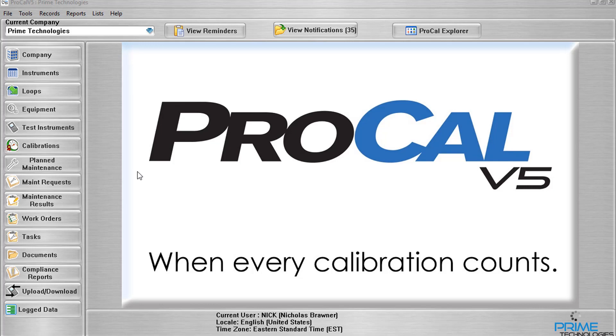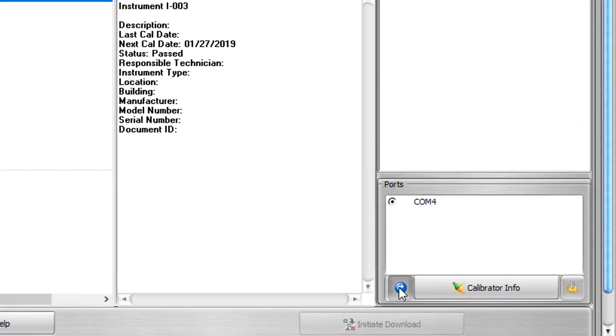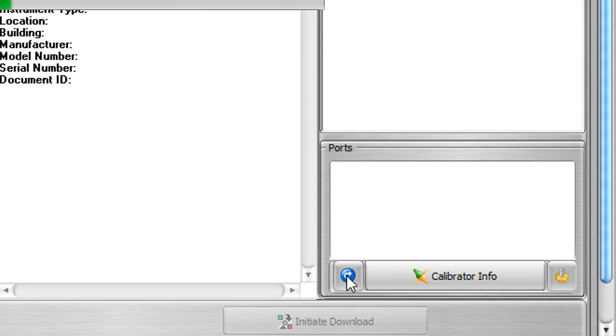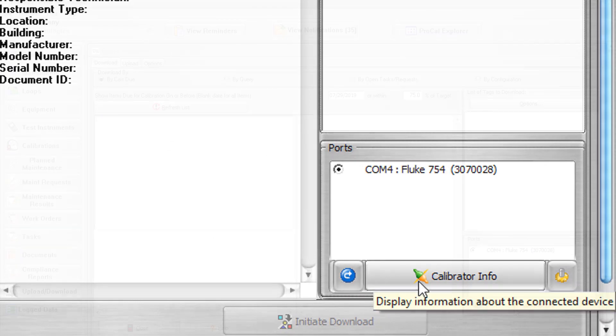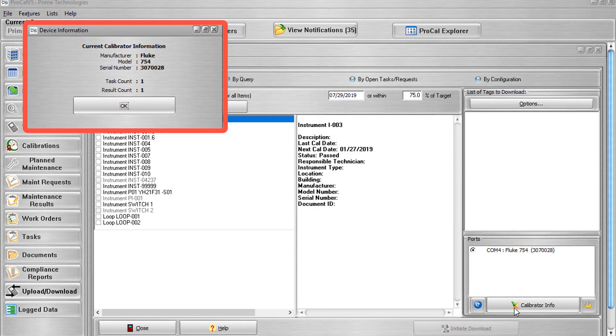To open the Field Calibrator Utility, select the Upload Download button on the left side of your screen. Once the screen is open, you can see evidence of your connected calibrator within the Ports section in the bottom right corner. Initially it will display the COM port which your calibrator is connected to. Selecting Refresh Ports will refresh the section to display the calibrator model and serial number. Selecting Calibrator Info will display the Manufacturer, Model Number, Serial Number, Task Count, and Result Count.